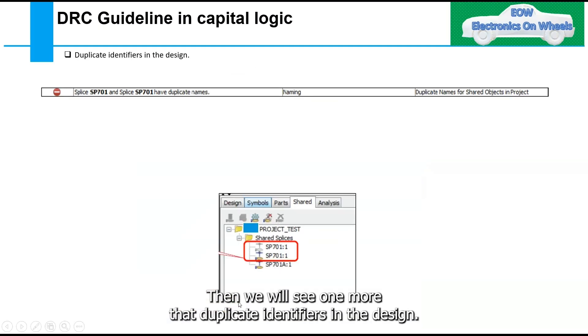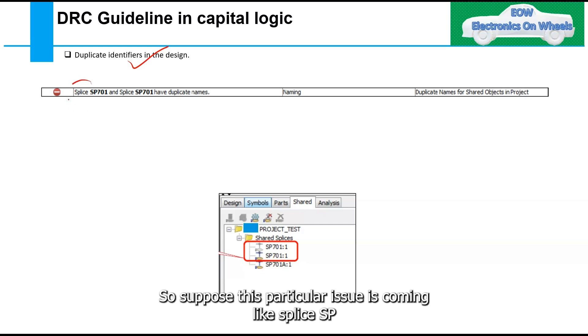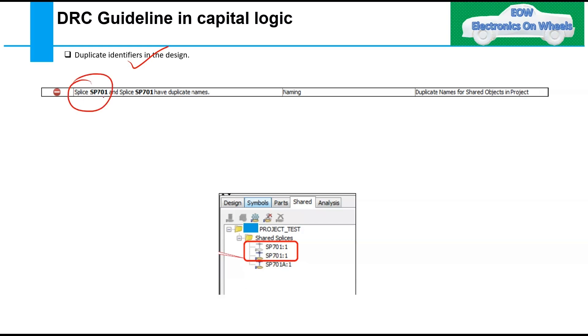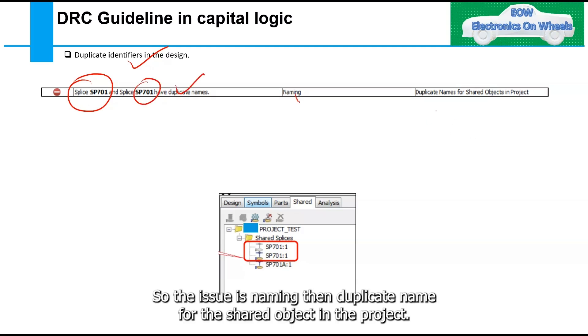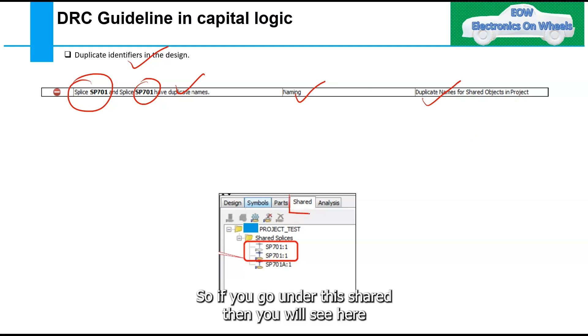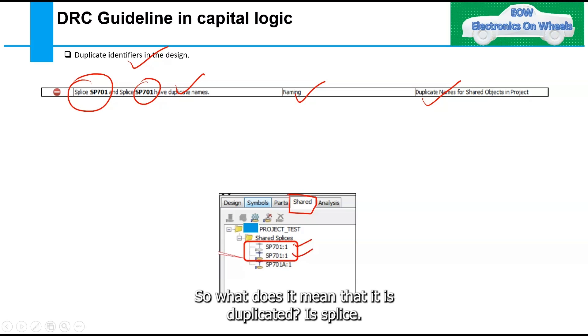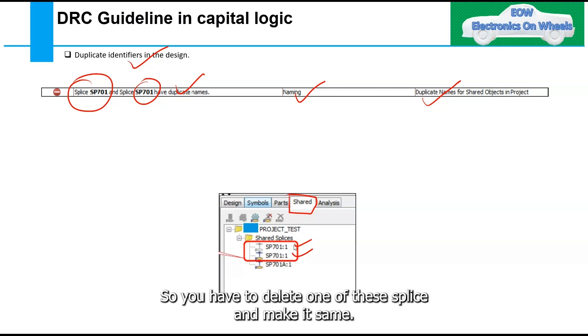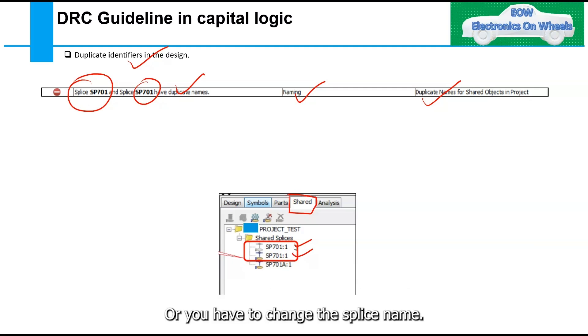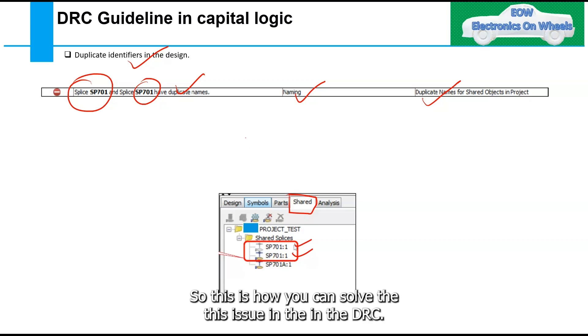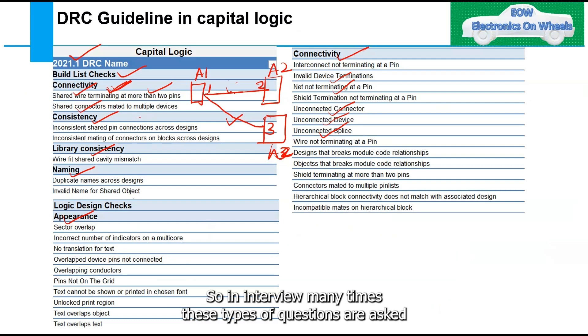Another DRC example is duplicate identifiers in the design. For instance, splice SP701 appears twice with the same name — the issue is flagged under naming as 'duplicate name for shared object in the project.' Under the shared view, you can see SP701 listed twice. To fix it, either delete one splice or rename it to remove the duplication.